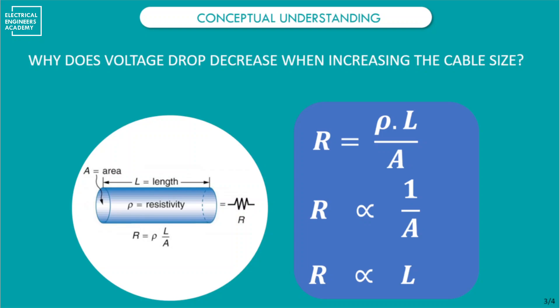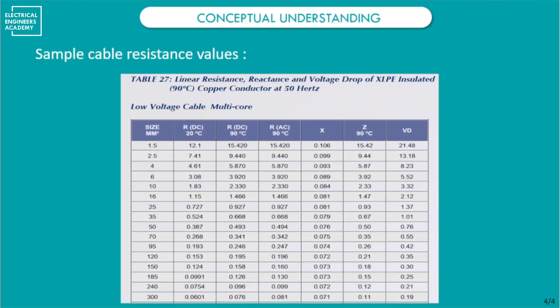Here we can see a sample datasheet from one cable manufacturer. You can clearly see that as the cross-sectional area of the cable increases, resistance decreases, and ultimately the voltage drop value of that cable decreases. This confirms that resistance is inversely proportional to the cable's cross-sectional area, and therefore so is the voltage drop.